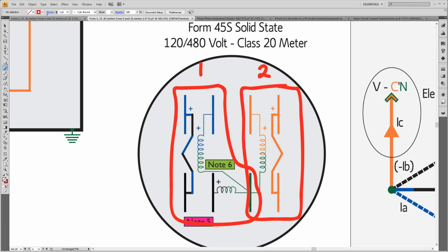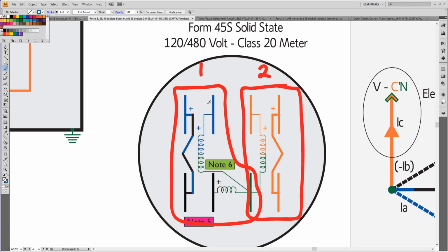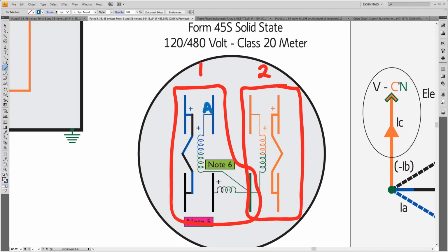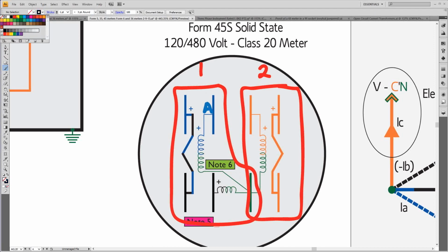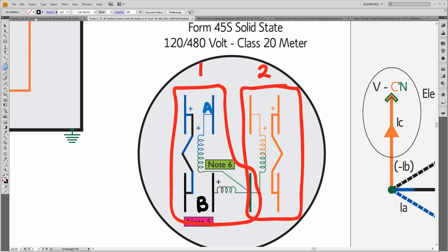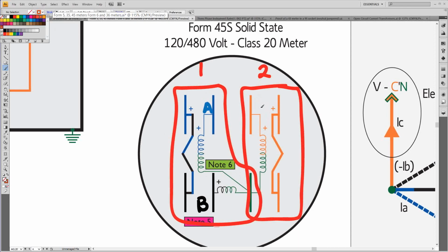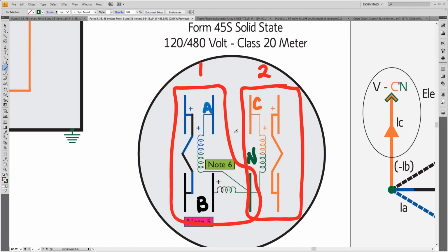The potential coil is connected from, if you remember how our socket was wired, it has a phase here. Socket was wired A and B, and then C. And I'll get this one right this time, Kevin. Neutral here. So that's how the socket's wired. And so I pull the 5S out and plug this meter into it. And what I end up with now, like I say, the same current flows in this current coil in the meter that it has in all 3 elements. That hasn't changed.